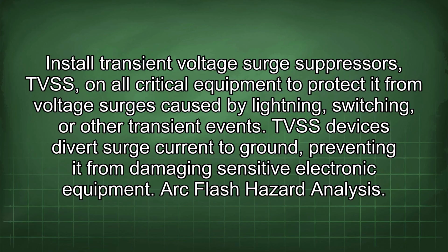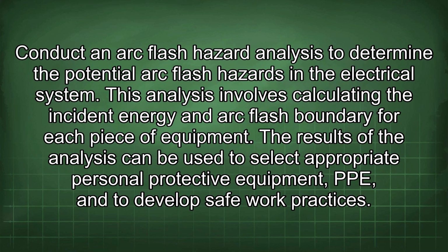Arc flash hazard analysis. Conduct an arc flash hazard analysis to determine the potential arc flash hazards in the electrical system. This analysis involves calculating the incident energy and arc flash boundary for each piece of equipment. The results of the analysis can be used to select appropriate personal protective equipment, PPE, and to develop safe work practices.